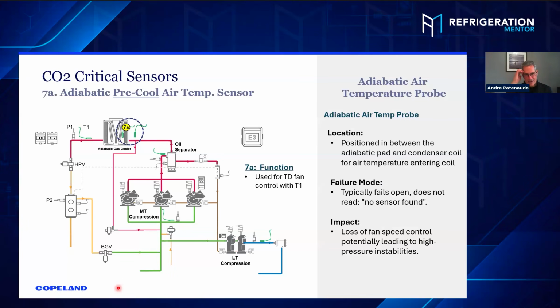Okay, adiabatic gas cooler pre-cool sensor. We debated a lot on what we were going to call this sensor, but we decided on pre-cool sensor. 7A location. That sensor is installed between the adiabatic pad, the gray here, and the angled aluminum tube, your actual coil. That's where it's positioned. It typically fails open, no sensor found. It's used for TD fan control.